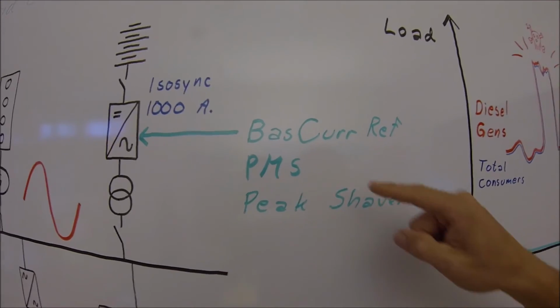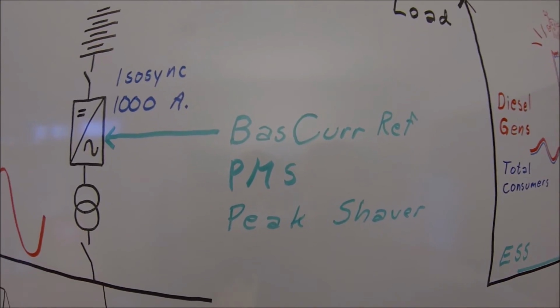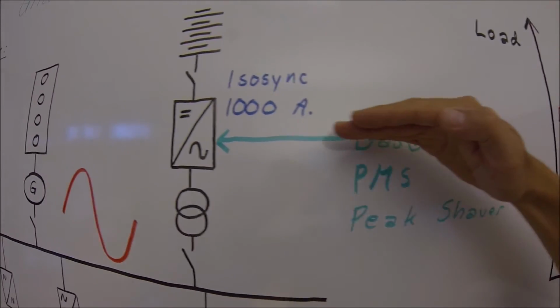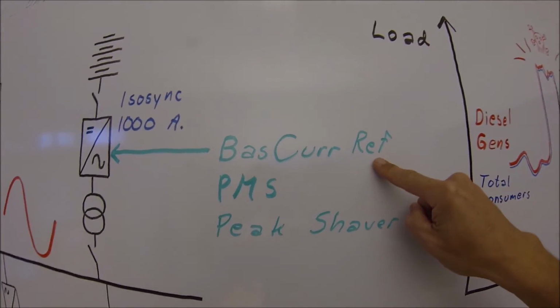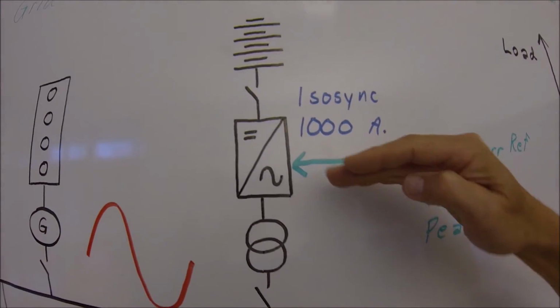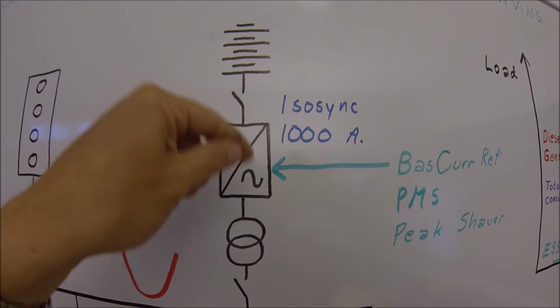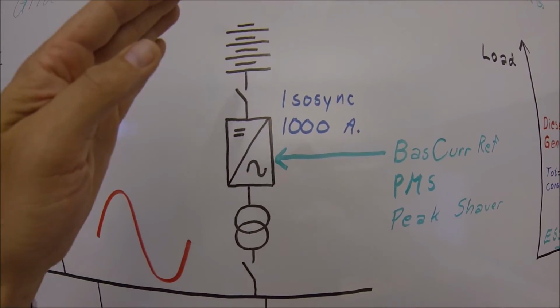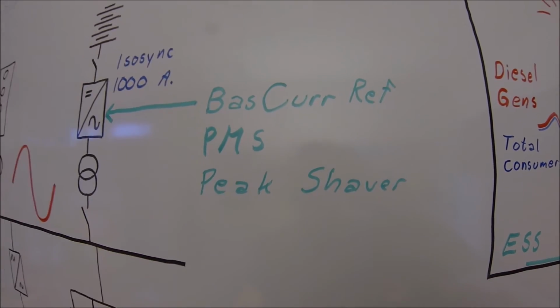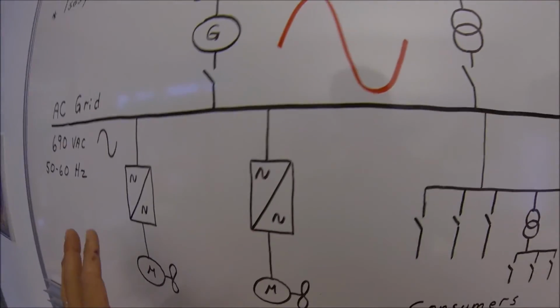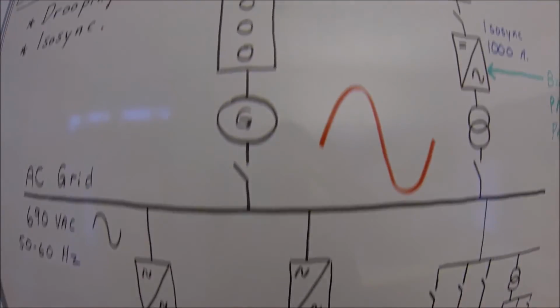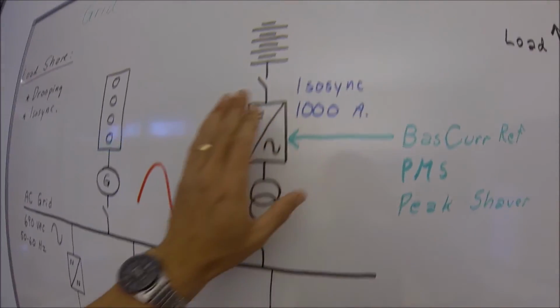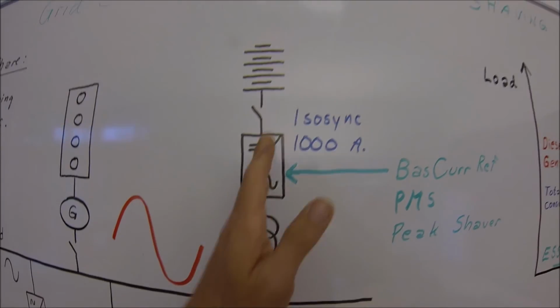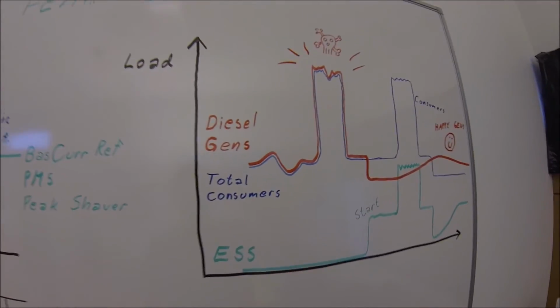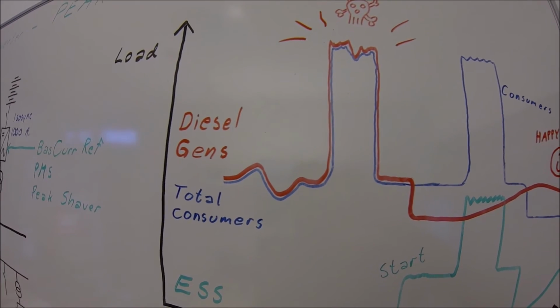To control this, you need a PLC, a power management, which gives the power reference to the drive, the base current reference. We will give the drive a command how many ampere should go to the grid or be taken from the grid. And the power management system is looking at total consumption on the grid and looking at these abrupt changes. And to protect the diesel generator, it gives a command to the energy storage to take these big and rapid changes.